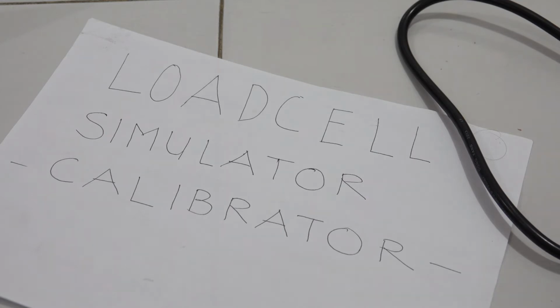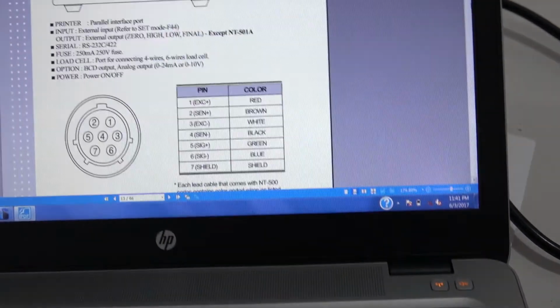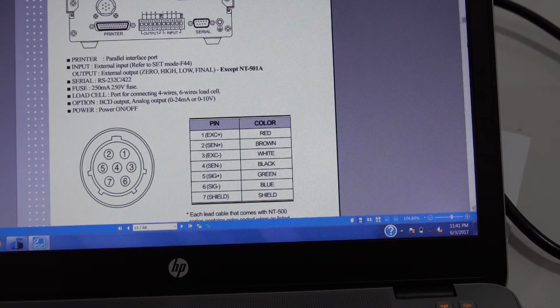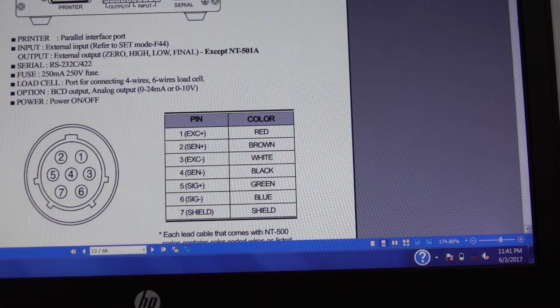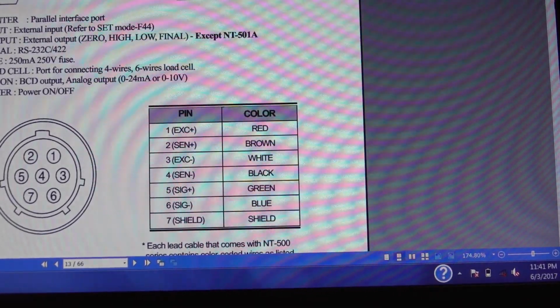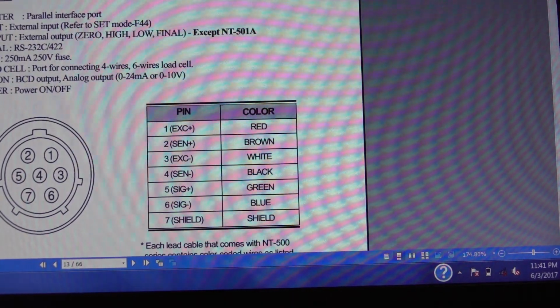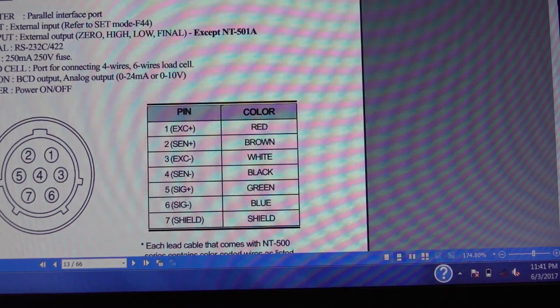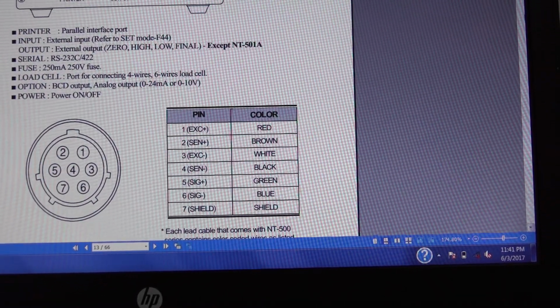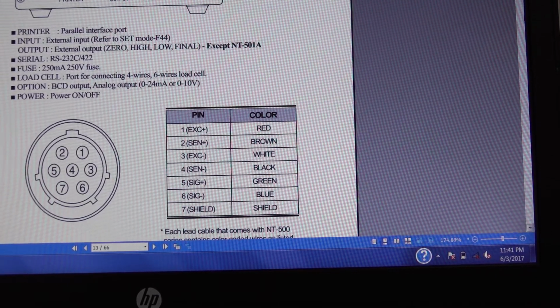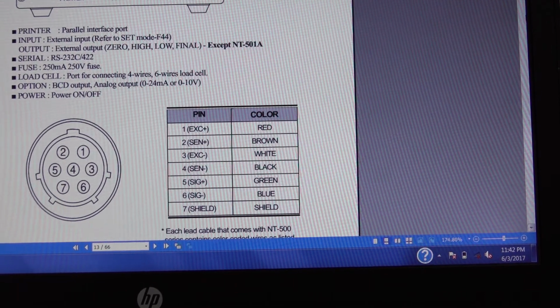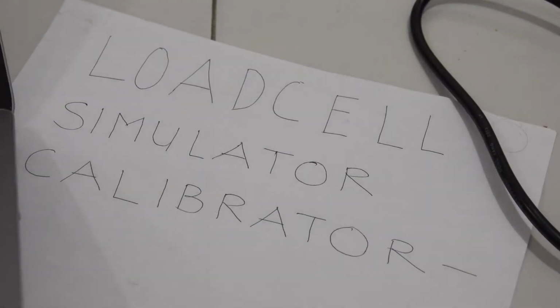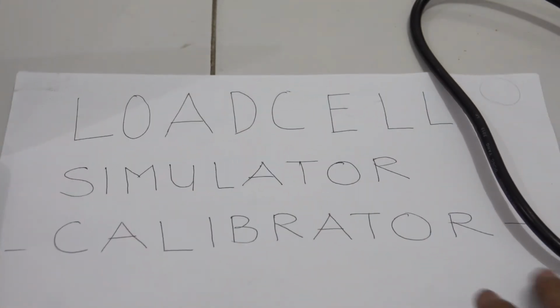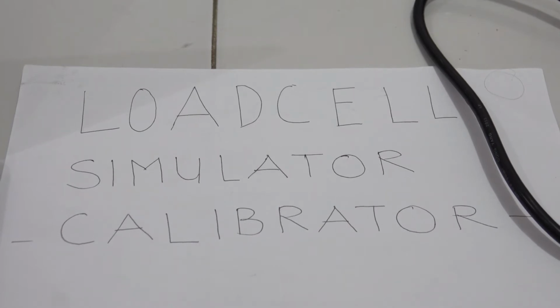Yeah, the cable seal. Okay, I have a sample here, the user manual of the load cell indicators made by CAS. You can download it from their official website. As you can see, the pin numbers and the colors are really different to other indicators, of course. So be careful about the colors, because my experience shows that if I accidentally connect the wrong colors, the reading is not correct. Yeah.